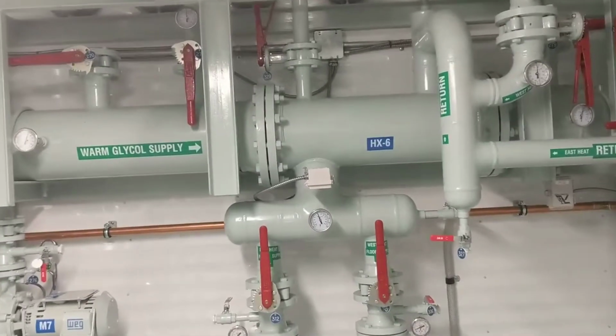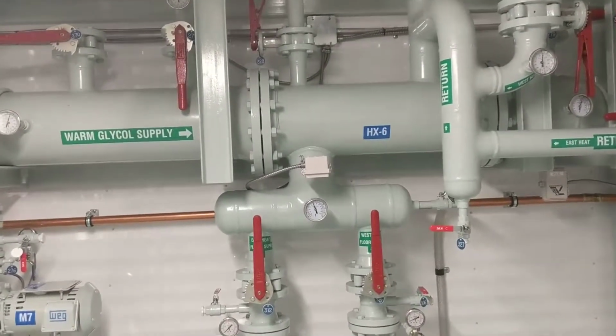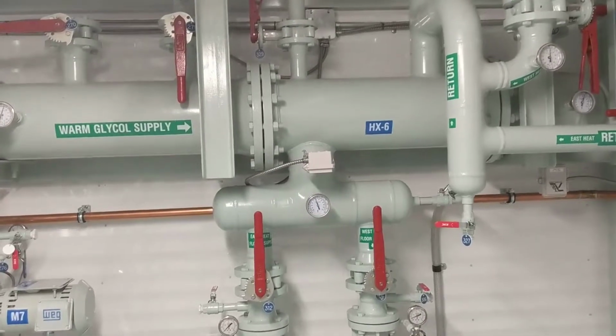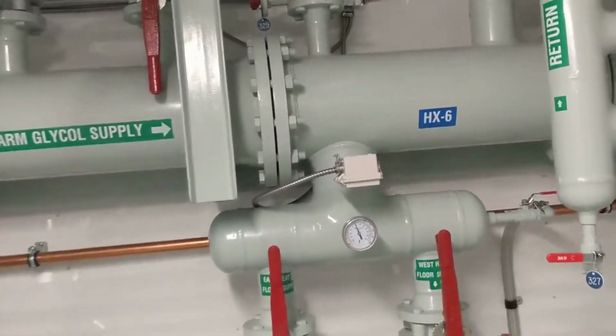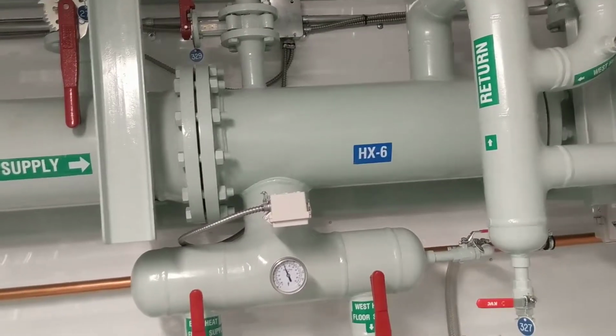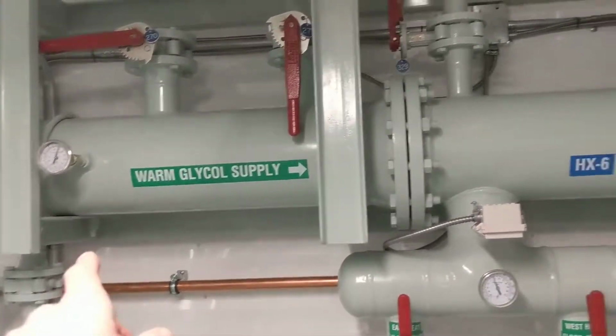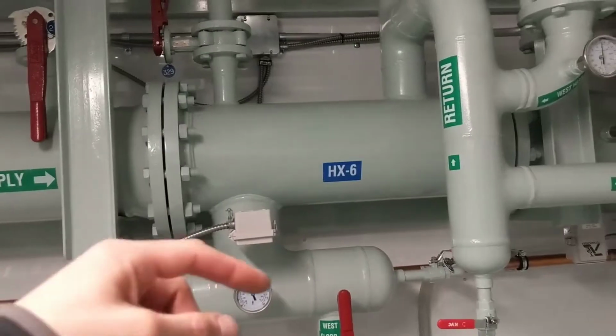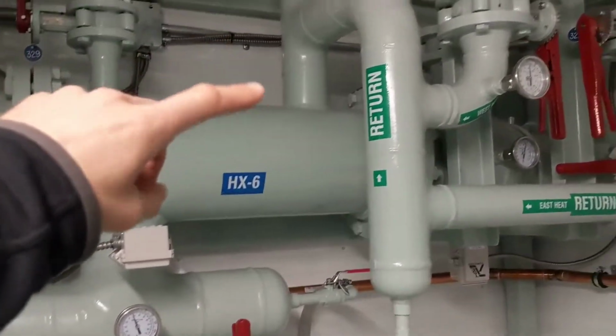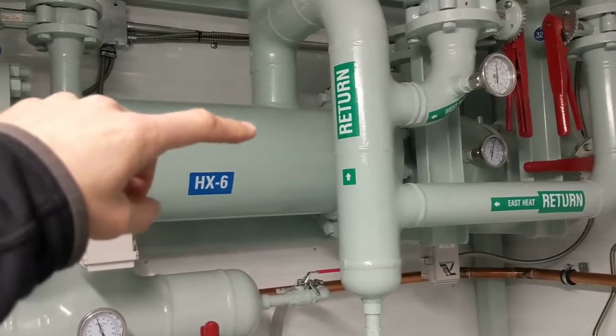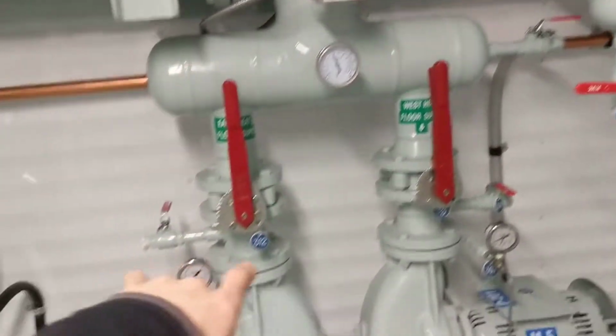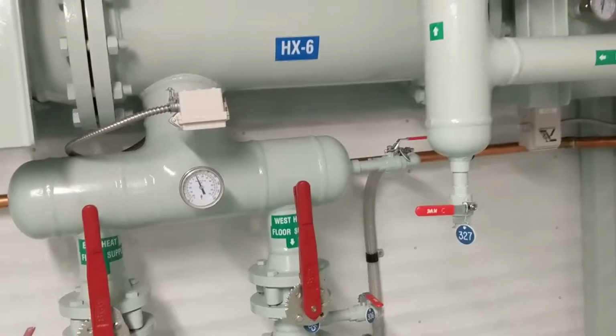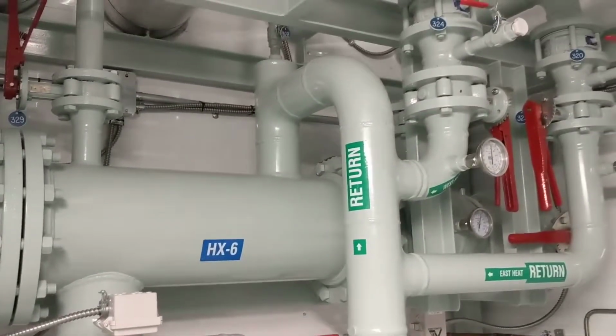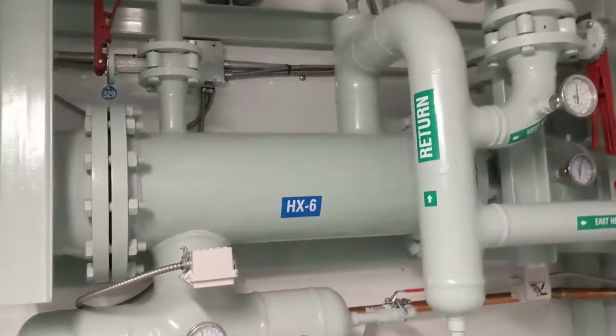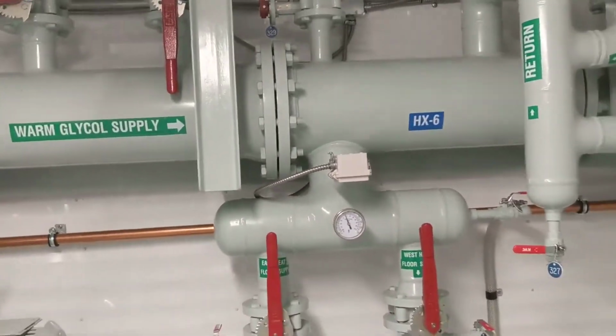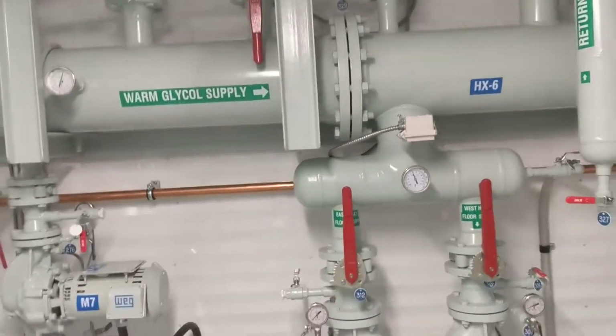Over here we've got HX6, and that does the warm floors for the two arenas. So it's a shell and tube heat exchanger. You've got warm glycol supply flowing through it this way, and you've got the brine flowing down through it this way. These pumps are feeding each of the floors, and that's how you're putting the heat into, or warming up, the brine for each of the warm floors.